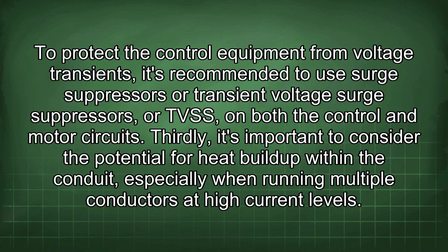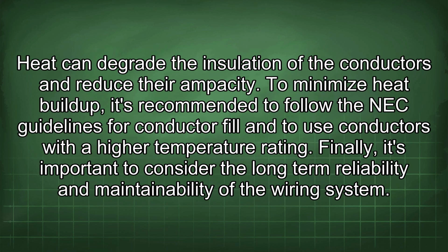Thirdly, it's important to consider the potential for heat buildup within the conduit, especially when running multiple conductors at high current levels. Heat can degrade the insulation of the conductors and reduce their ampacity. To minimize heat buildup, it's recommended to follow the NEC guidelines for conductor fill and to use conductors with a higher temperature rating. Finally, it's important to consider the long-term reliability and maintainability of the wiring system.